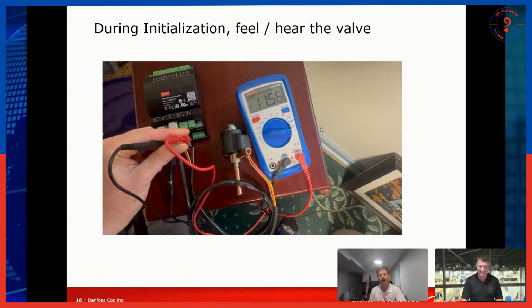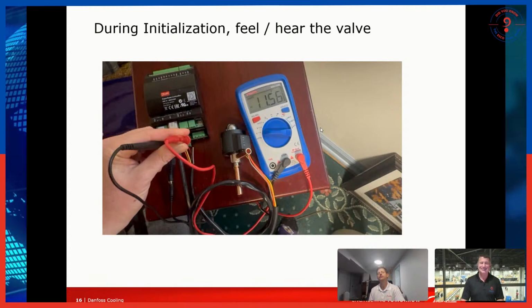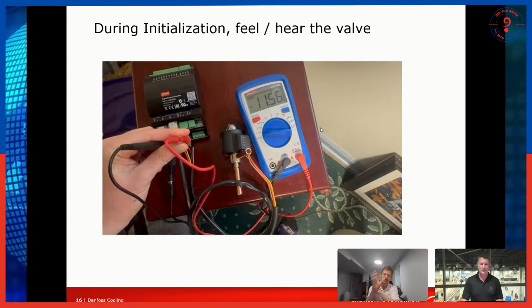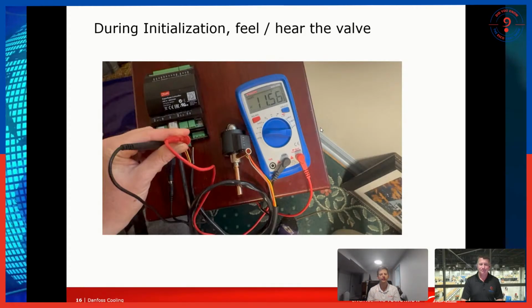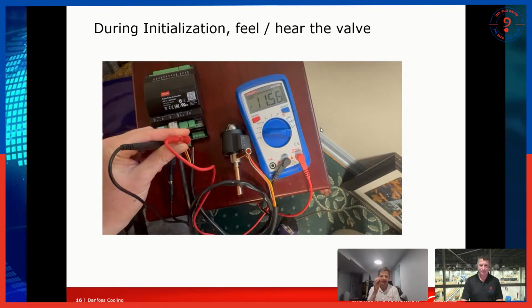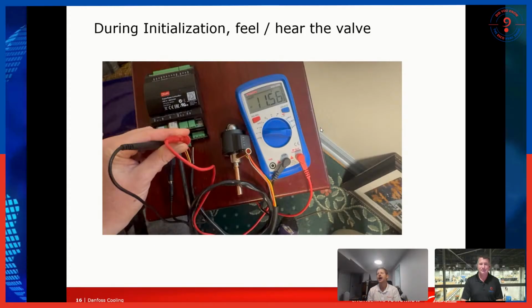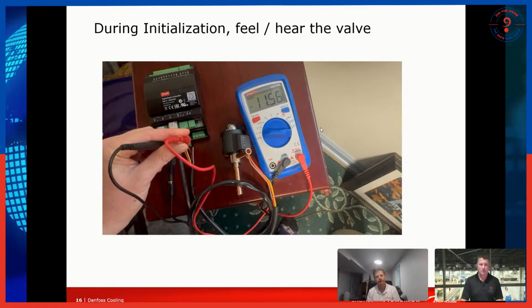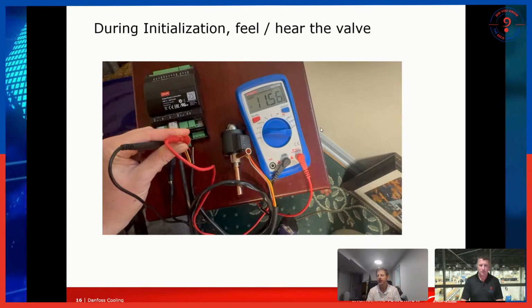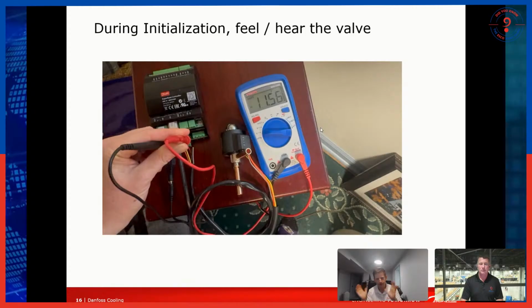It's kind of like, if you're familiar at all with operating a VFD, it brings in AC power, and then it sends pulses of DC power out to whatever motor it's controlling, but it does it so fast, it might be sending out at 60 hertz, 60 times a second. And that way, to pick it up, you need your multimeter set to AC. Otherwise, either it'll just say 0 or it'll be confused, or it depends.